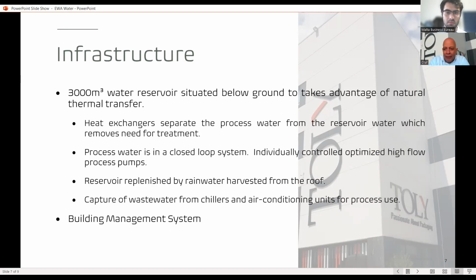Comparing this to the previous system, we had a system with 30 cubic meters of water, and we were chilling the water directly. It went straight into our chillers, reducing the temperature to 7 degrees, then was pumped into the machines, coming back at 24, 25, 26 degrees, and going through that cycle all over again. So we had a delta of about 19 degrees.